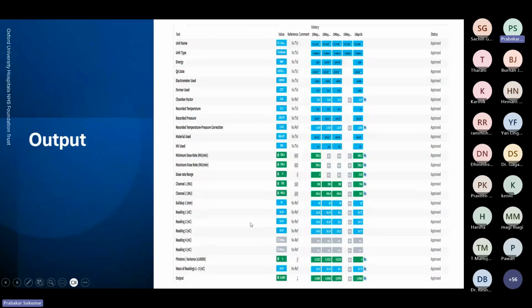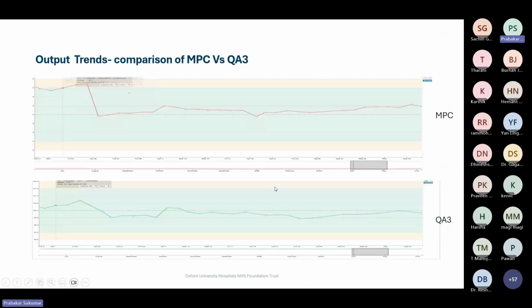And you can use the trends chart as well. So output, basically we will be using ion chamber measurements, but nowadays we are using the MPC as a part of the daily QA, particularly in Varian machines, and we are using the QA3 as backup data. If the MPC fails, what is the backup data? So QA3 is basically our backup data. You can see how well both trend. You can see the chart that has been produced on the upper part. Okay.